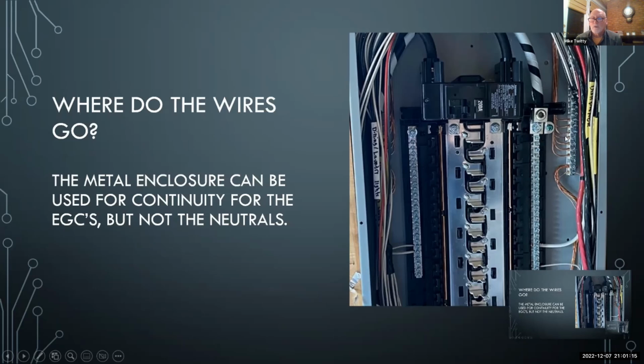Now, these equipment grounds can be on this bar and they can be on this bar or that bar. Equipment grounds can use the continuity, since this is bonded right here. This ties all this to the metal can. This can use the metal can as a conductor for these equipment grounds. It cannot be used for the neutral. The neutral has to go on the neutral bar, which has a tie bar here going to the other. So the neutral has to go through here. You can't put a neutral here and let the continuity of this metal can supply the continuity to this neutral on this bar.